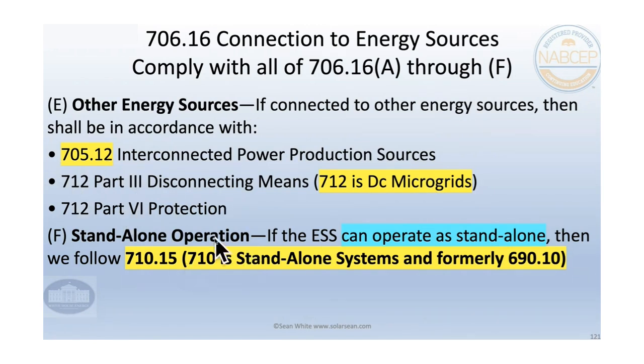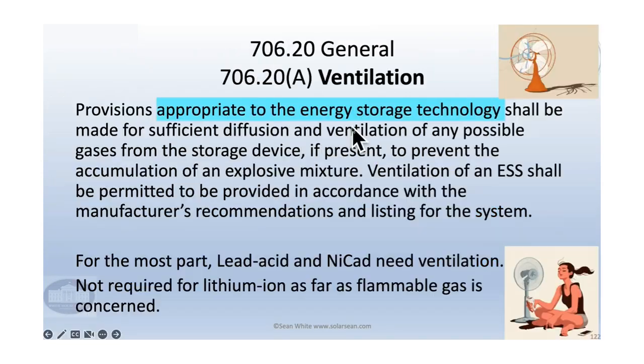And then standalone, there's a couple of things there that are kind of neat. Okay. Ventilation is for lead acid and NiCad. That's where when you overcharge these things, you get a flammable gas. In fact, even if you have a sealed lead acid battery, I know that some people writing the code say that if it's sealed, you don't even need the ventilation. I've always thought it's still a good idea because if you accidentally overcharge it, you still might get some kind of gas, but some of these sealed batteries would be just not too flammable. But we're not really going to be seeing much in the way of lead acid, I don't think, anyway. And so we don't need the ventilation for the lithium ion batteries in general.